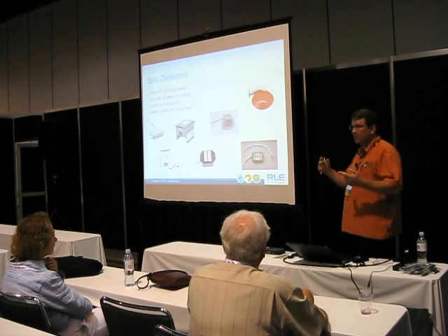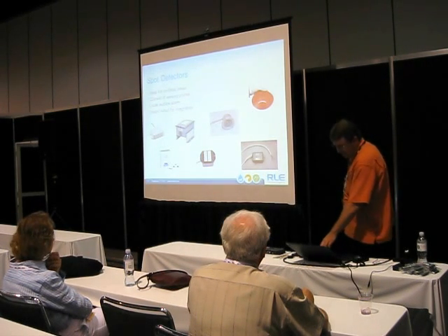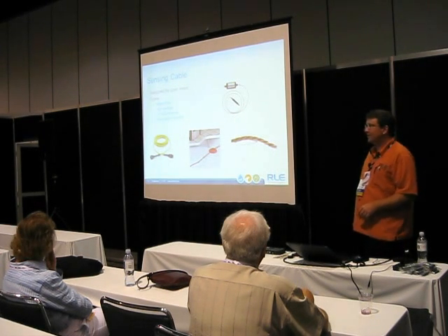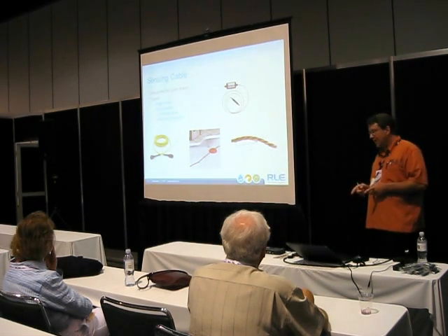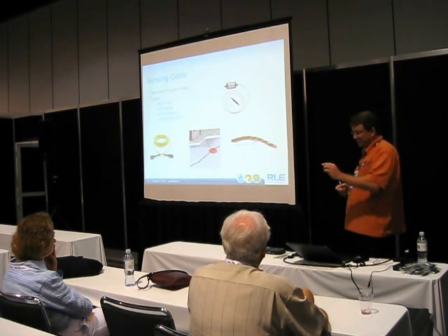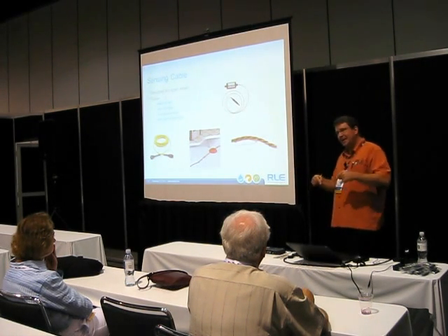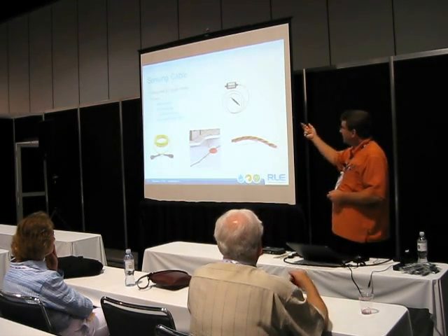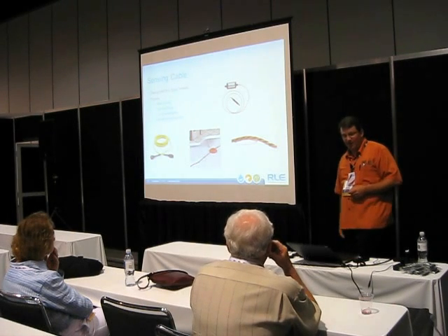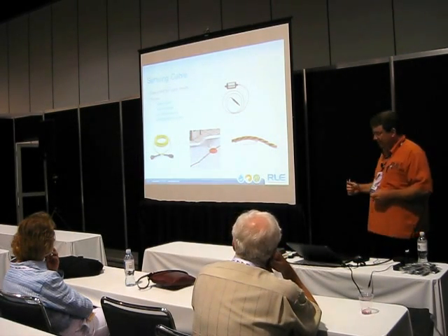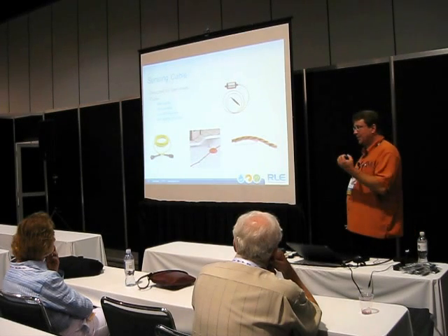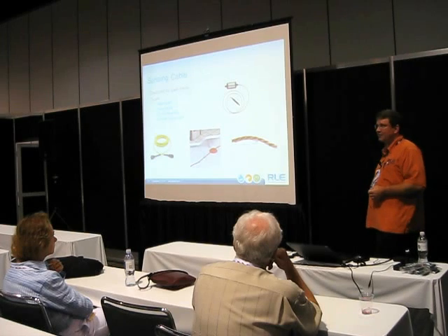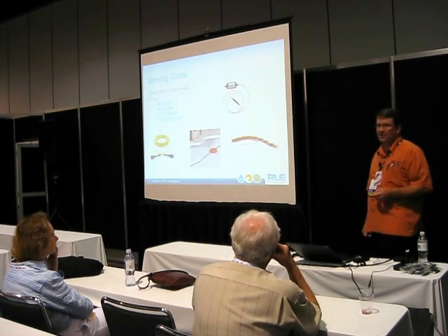Water just bridges those two probes and it creates a water condition. And then generally you'll integrate those into another system. Sensing cable is designed for those open areas, to encapsulate areas of concern. The nice thing about that is that as opposed to a single spot, you can run it around equipment that might be damaged, or around those sources of leaks. And what we really need to understand is that there are a few different types of leak detection cable available on the market. Mesh covered cables, and I have some samples you can look at when you're done, will retain moisture and are hard to dry. One manufacturer recommends you have a hair dryer on site to dry the cable after it gets wet. A lot of people don't have hair dryers on site.